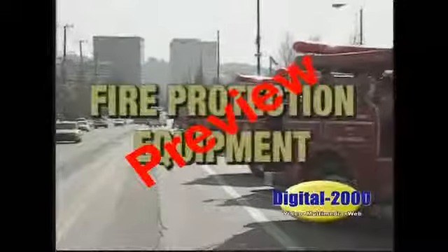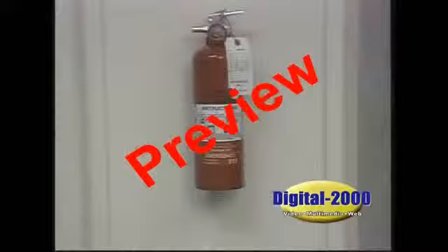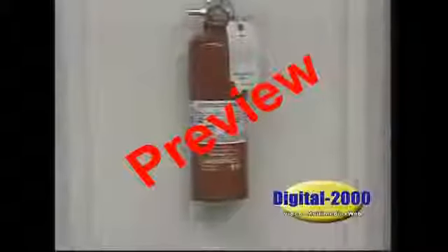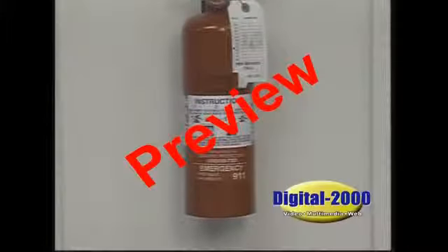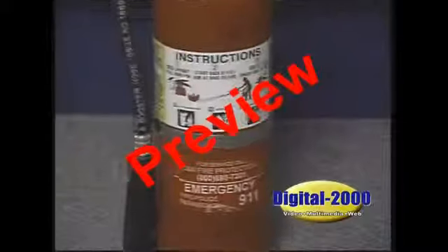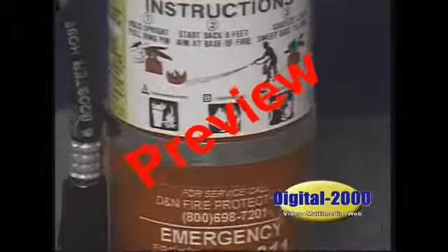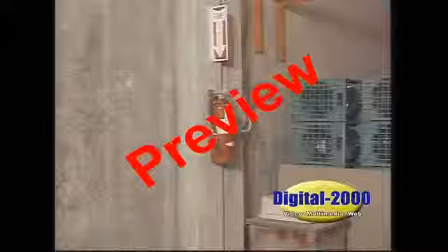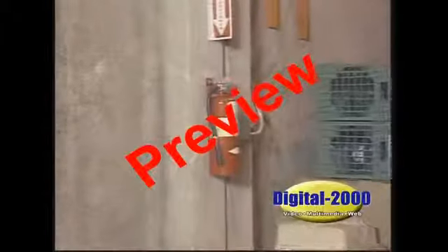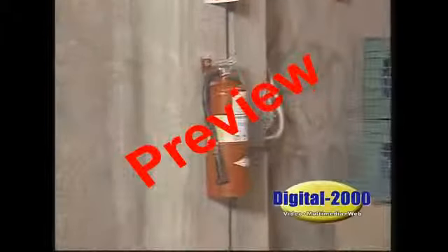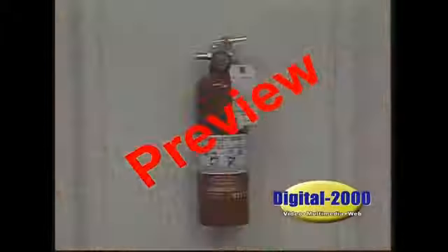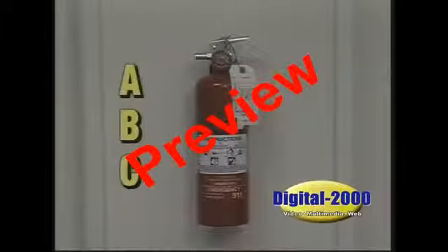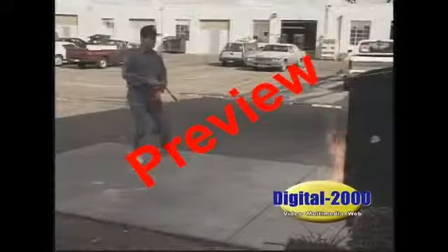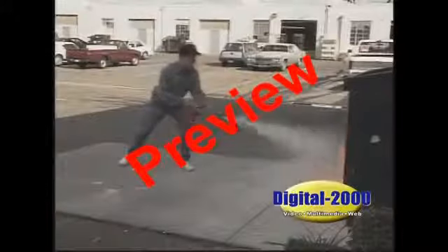Okay, let's take a look at some basic fire protection equipment. You've all seen fire extinguishers and probably know how to operate them, but let's review quickly. We'll explain only one type of extinguisher, the ABC dry chemical type. All extinguishers operate basically the same way, but each is designed to extinguish different types of fires. The ABC extinguisher means it will extinguish Class A fires, Class B fires, and Class C fires. It's a dry chemical pressurized with an inert gas.